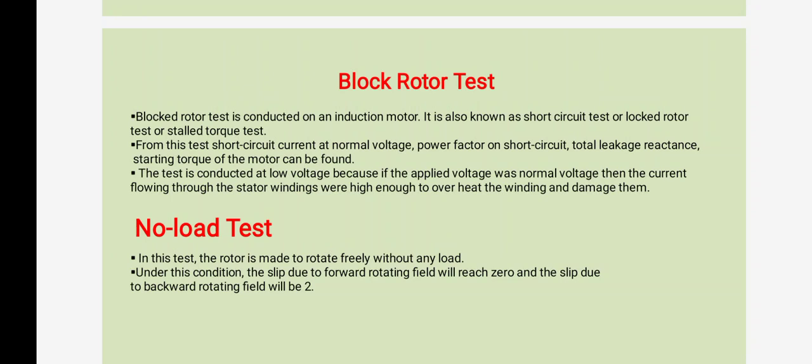Then there are two tests generally performed on the single phase induction motor. One is called the blocked rotor test, the other is called the no load test, to find the performance of the single phase induction motor. The blocked rotor test is conducted on the induction motor. It is also known as the short circuit test, locked rotor test or stalled torque test. From this test, the short circuit current at normal voltage, power factor on short circuit, total leakage reactance, and starting torque of the motor can be found.